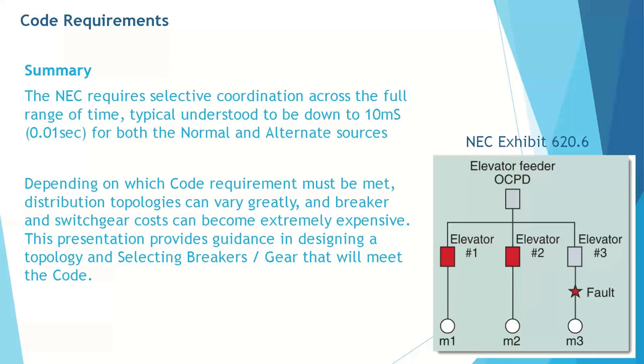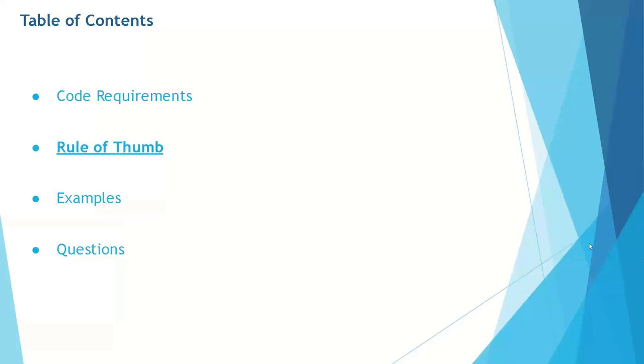There are also local AHJ requirements as some AHJs require selectivity only for the emergency systems and permit miscoordination to take out the parallel normal side. California, for example, only requires selective coordination down to 100 milliseconds on healthcare systems due primarily to the fact that maintenance staff is present around the clock. You will want to confirm your requirements and request a variance early if necessary, which we have seen happen quite a bit over the past few years.